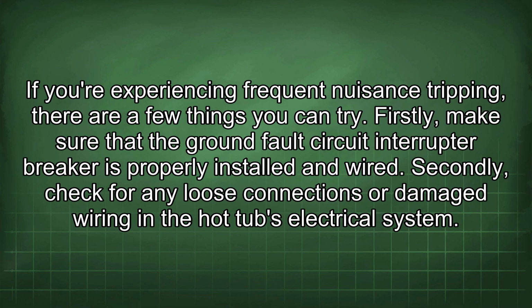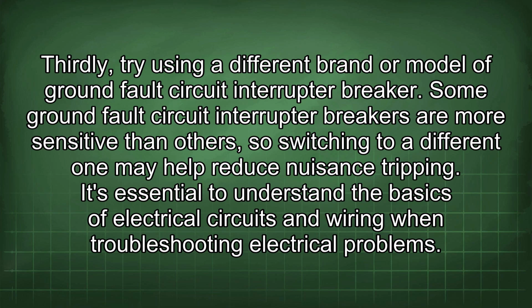If you're experiencing frequent nuisance tripping, there are a few things you can try. Firstly, make sure that the ground fault circuit interrupter breaker is properly installed and wired. Secondly, check for any loose connections or damaged wiring in the hot tub's electrical system. Thirdly, try using a different brand or model of ground fault circuit interrupter breaker. Some are more sensitive than others, so switching to a different one may help reduce nuisance tripping. It's essential to understand the basics of electrical circuits and wiring when troubleshooting electrical problems.